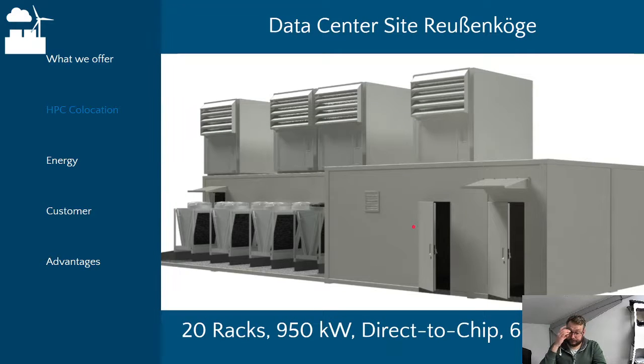So this is the HPC module. You see, we still have an air-cooled system on top. This is just due to the fact that although the direct-to-chip water cooling is allowing for a lot of energy to be directly transferred away from the chip, not all of the energy can be moved directly into the water. So we have about 20% that still needs to be moved away over the air circle, with nearly 1 megawatt capacity installed. So that still results in about 200 kilowatts. So there's still a lot of air cooling going on in this configuration. The water circle itself is moved out, then it goes to these recooler units, and they cool the warm water down.